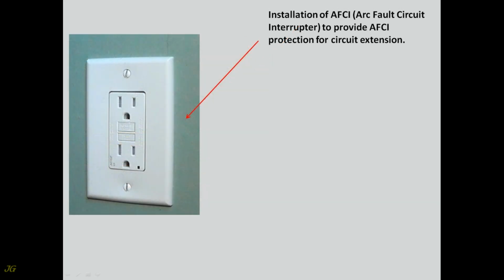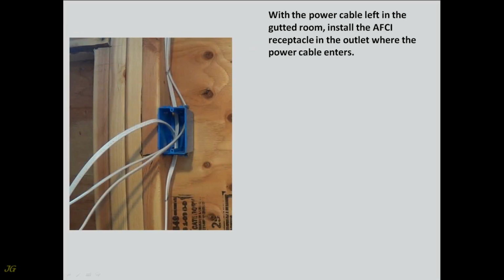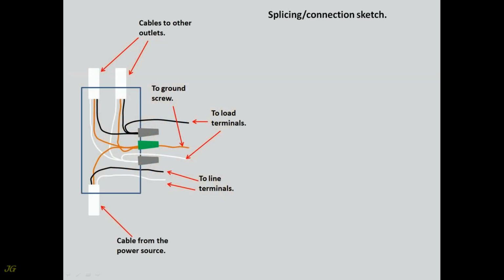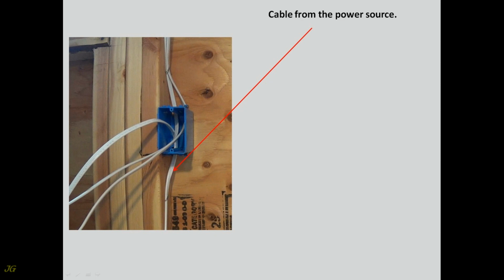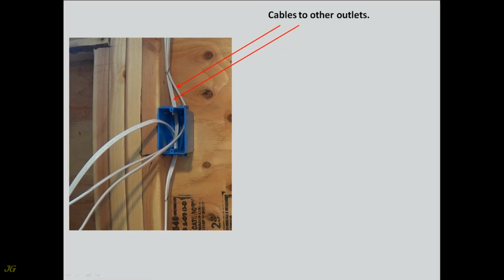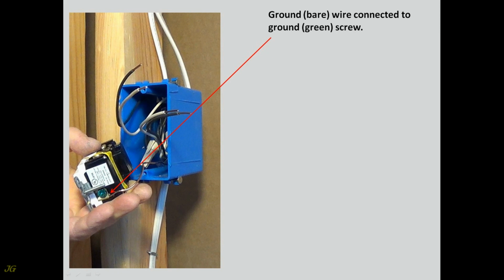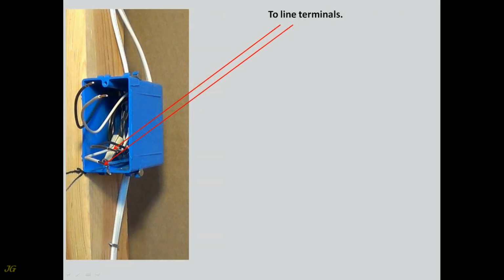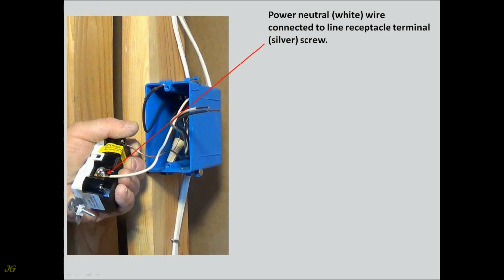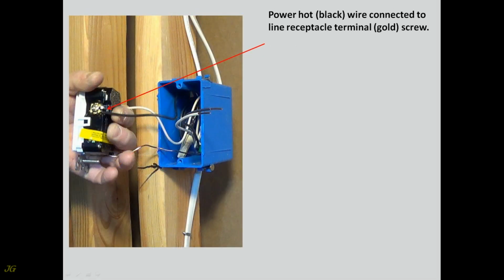Installation of AFCI, arc fault circuit interrupter, to provide AFCI protection for circuit extension. With the power cable left in the gutted room, install the AFCI receptacle in the outlet where the power cable enters. Splicing, connection sketch. Cable from the power source. Cables to other outlets. To ground screw. Ground, bare, wire connected to ground, green, screw. To line terminals. Power neutral, white, wire connected to line receptacle terminal, silver, screw. Power hot, black, wire connected to line receptacle terminal, gold, screw.